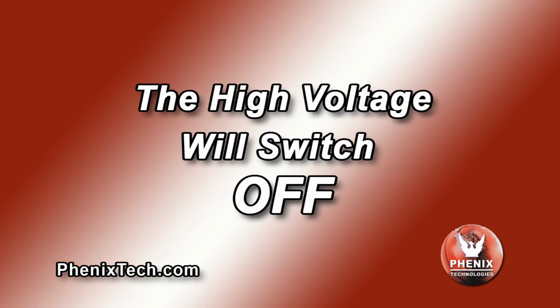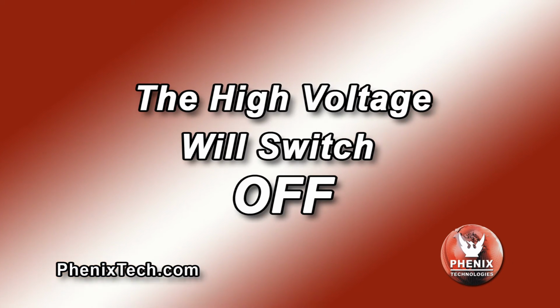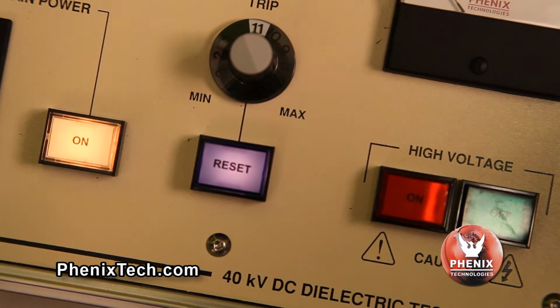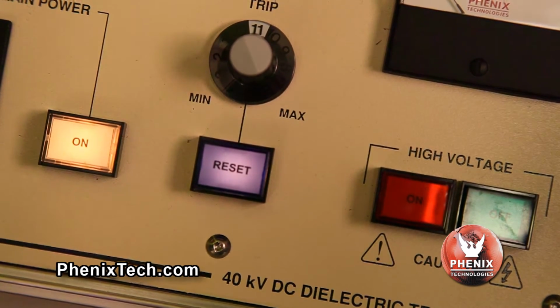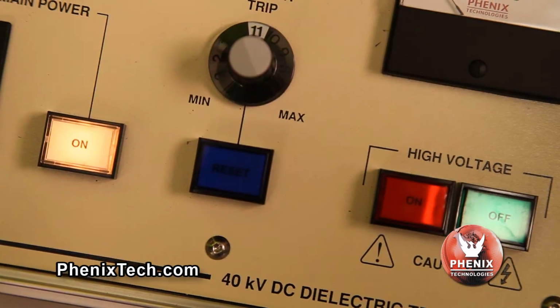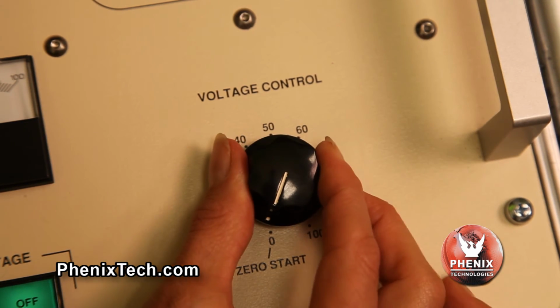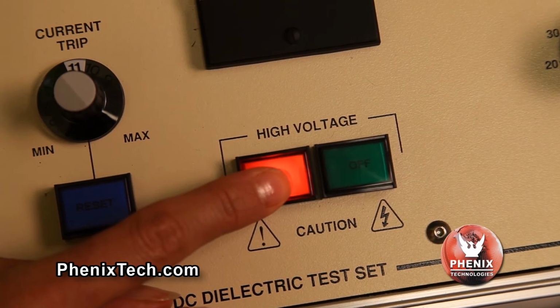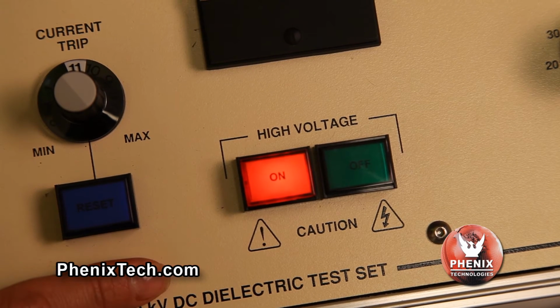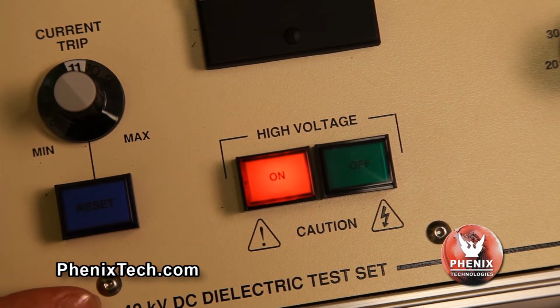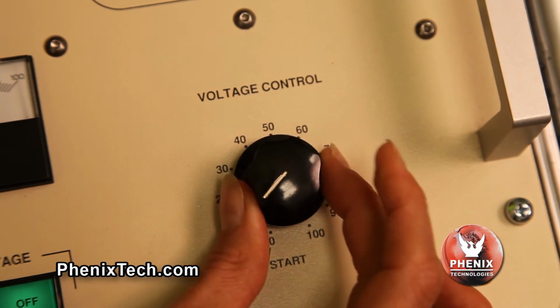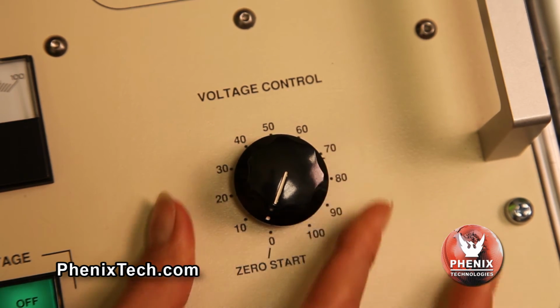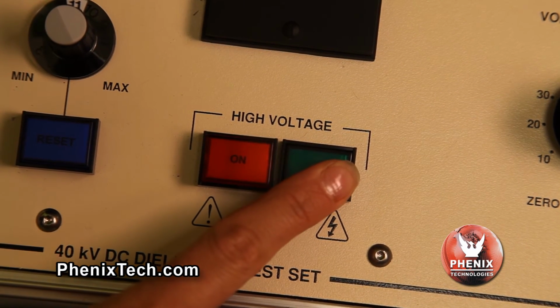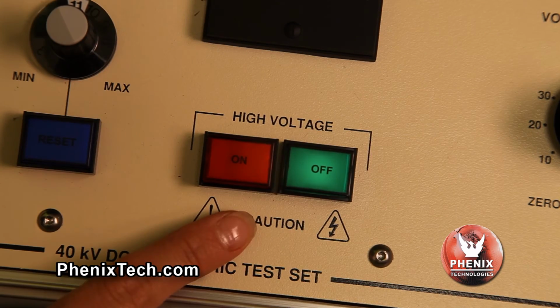point, the overload will activate and the high voltage will switch off. To enable the high voltage on, the overload reset button must be depressed and the voltage control dial must be returned to 0. Then press the HV on button momentarily to turn high voltage back on. Lower the voltage control to 0 after testing is completed. Depress high voltage off button. The high voltage indicator light will go out.